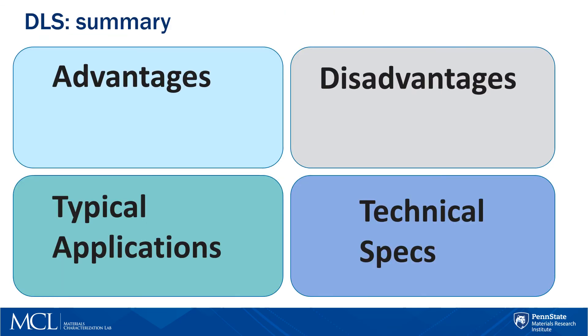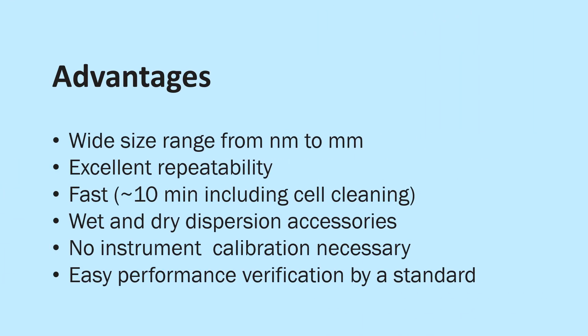To summarize, the advantages of laser diffraction include a very wide size range from nm to mm, excellent repeatability, very fast measurements, and wet and dry dispersion accessories are available. We do not need to calibrate the instrument, but it is very easy to verify its performance using a standard.